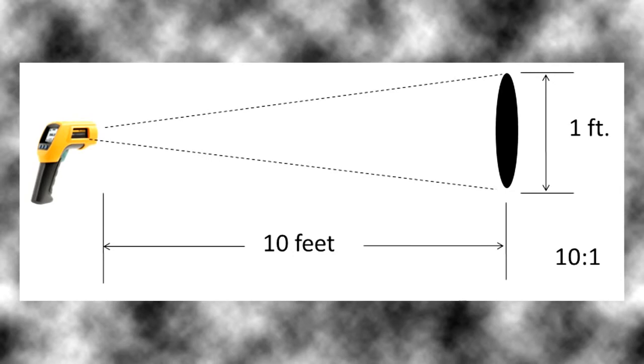For example, if we had a device with a ten to one distance to spot size ratio and we were ten feet from the target, we would take that ten feet divided by the ten to one ratio and that would give us a one foot diameter circle. So the laser would be pointed at the center of this one foot diameter circle and the IR thermometer would be measuring the average temperature of that one foot diameter circle.